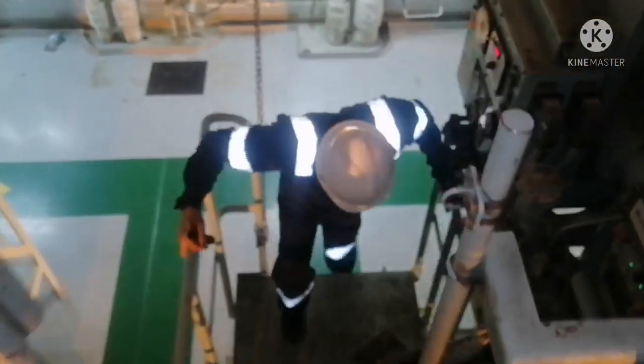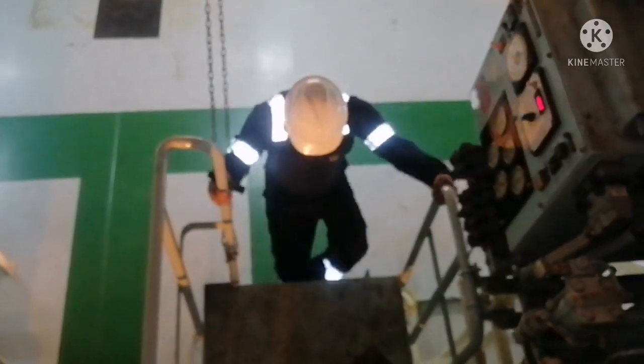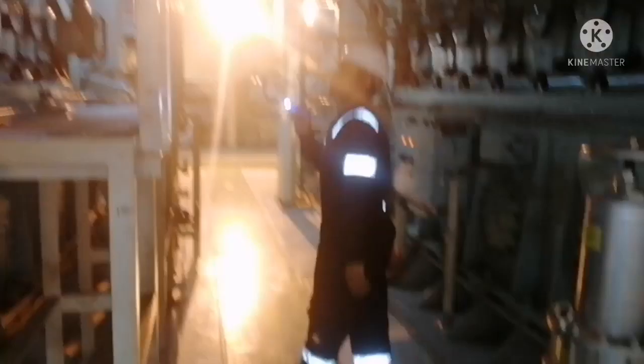So this is your running generator. For a running generator, all these things you have to check. Just have a visual round on all the generators. Whichever generator is running, we have to ensure there are no abnormalities, no leakages, nothing. All parameters are in normal conditions. All temperatures are normal, lube oil pressures and fuel oil pressures are normal.